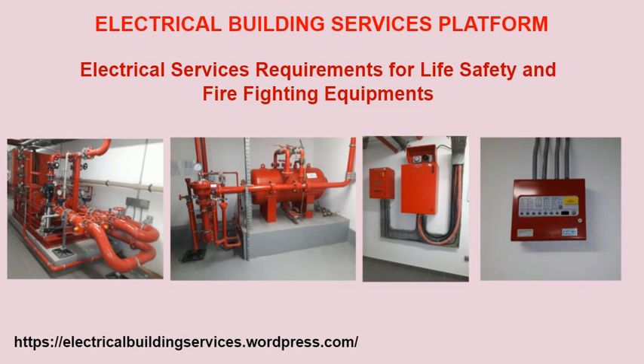Number 22. The primary and secondary power supply cables should be terminated in a changeover device located within the plant room, housing the life safety and fire protection equipment. Number 23. The changeover device should automatically effect the transition from the primary to the secondary supply if the primary supply to the particular plant fails.